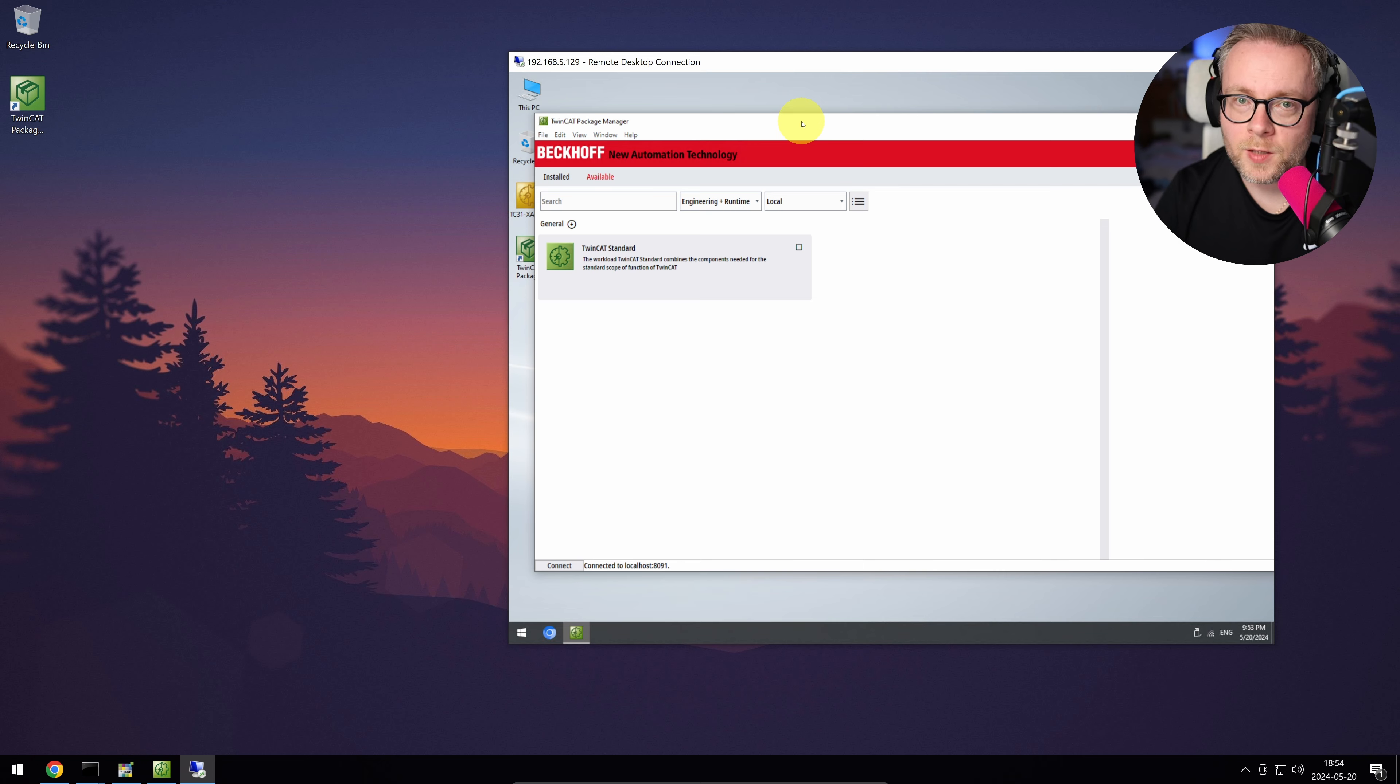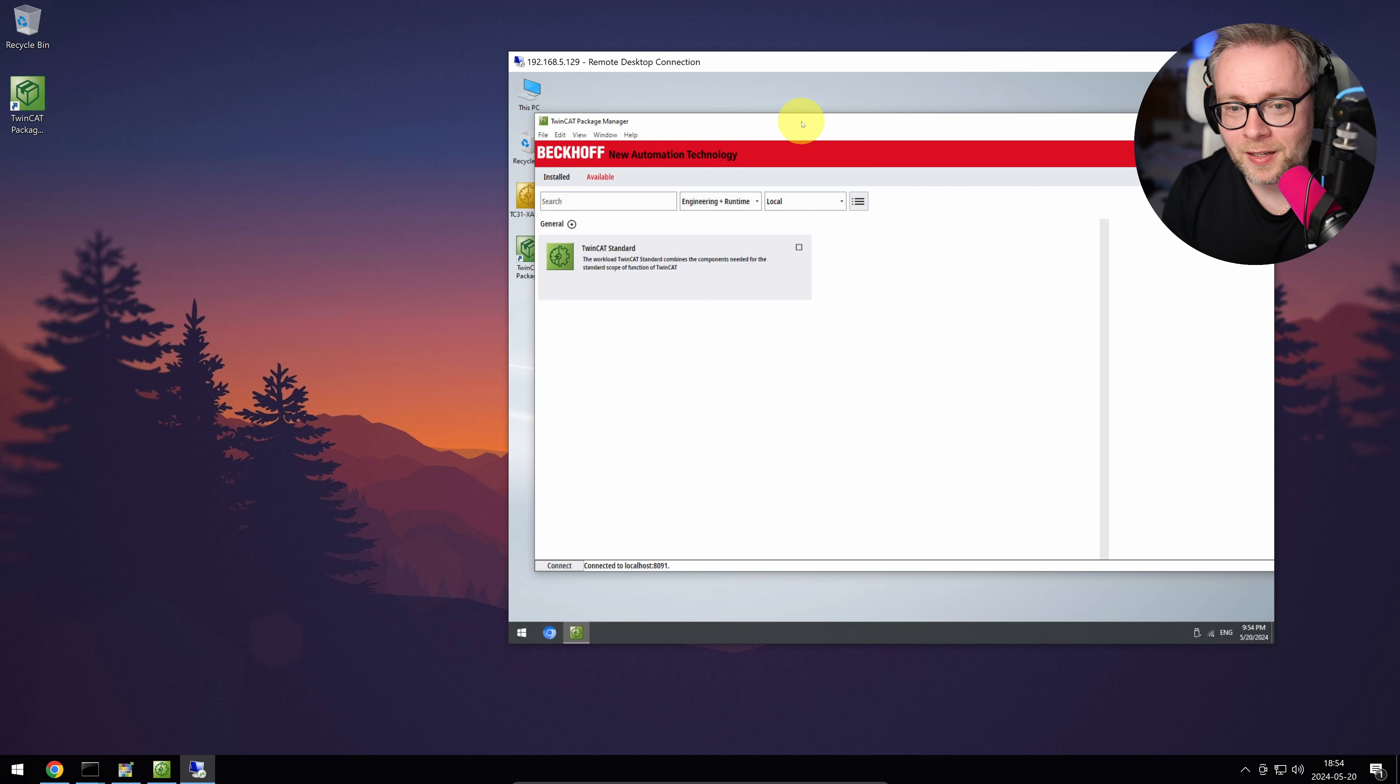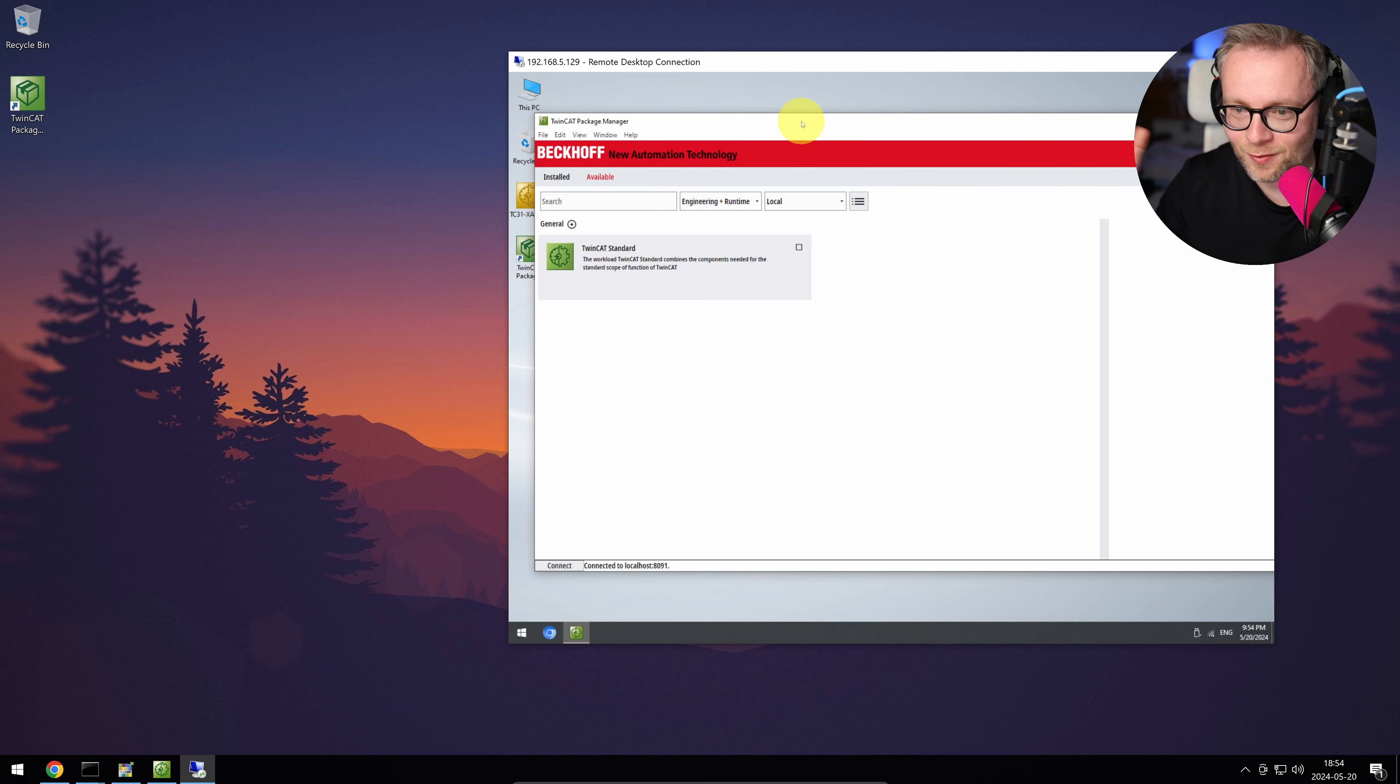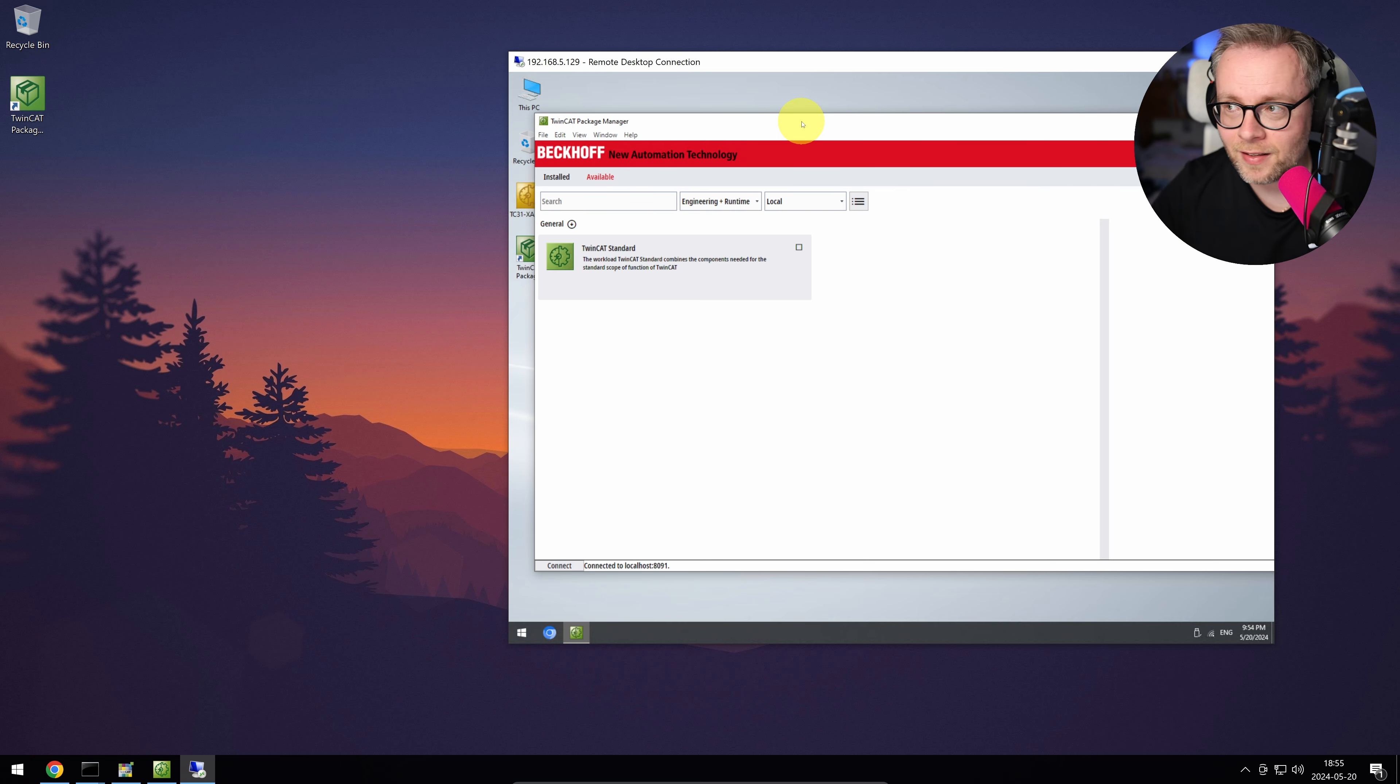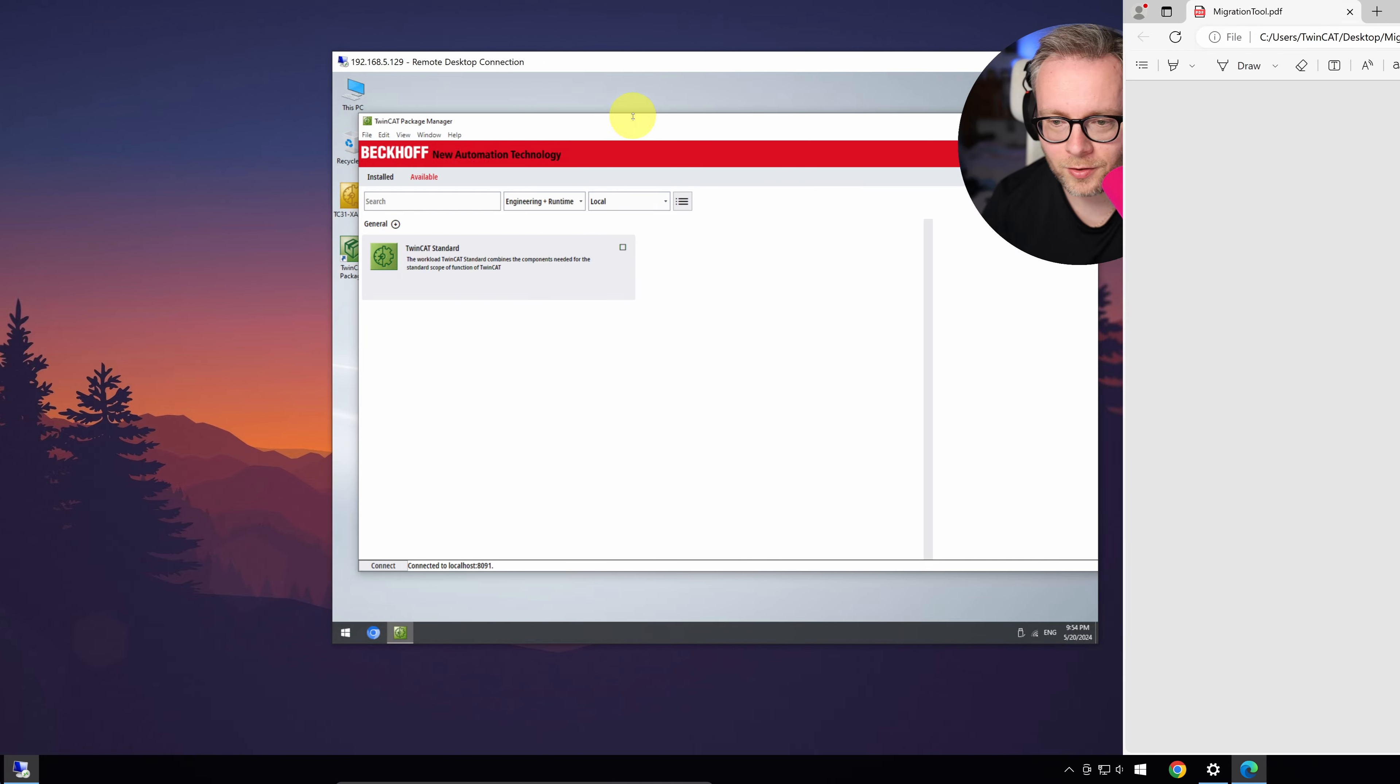Okay, I spent way, way, way more time than I should to get rid of the old TwinCAT 4024 from this PLC. So that's amazing that for a one and a half billion euro company that they can't provide proper instructions or a proper script or anything official of how to get rid of the old version of TwinCAT. And I spent so much time with this, going into the registry, deleting files manually and... That I'm not going to tell you what I did. My recommendation here instead is to get a clean image from Beckhoff for your PLC. And when I say clean, I mean image of the operating system without TwinCAT pre-installed. Just Windows. Just operating system. Nothing else.